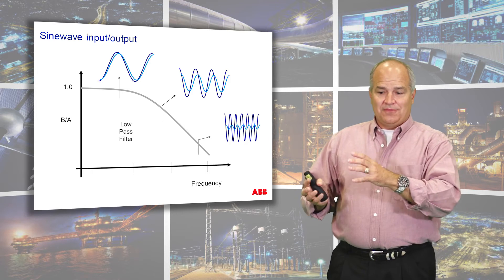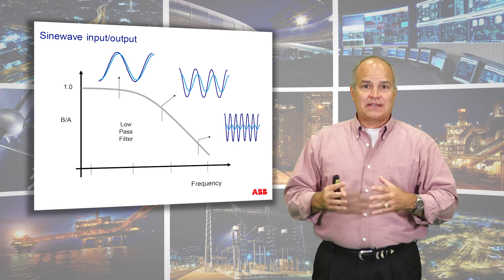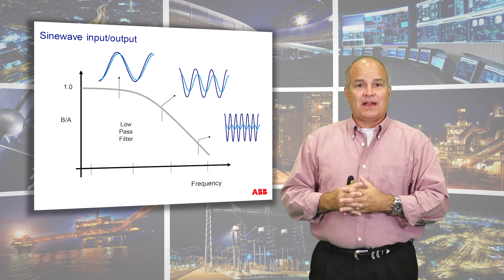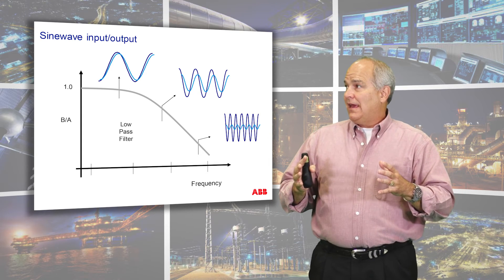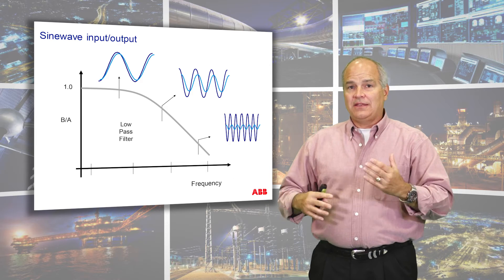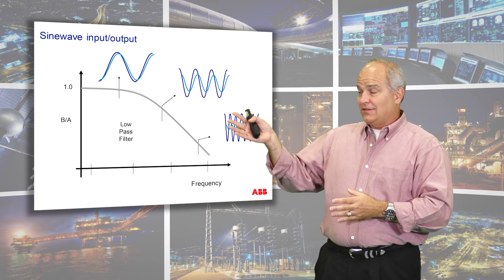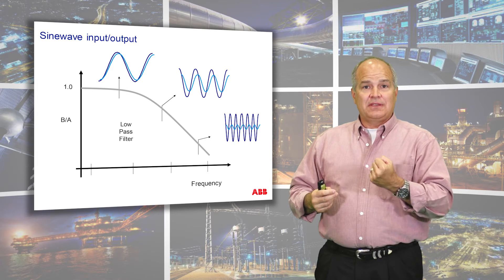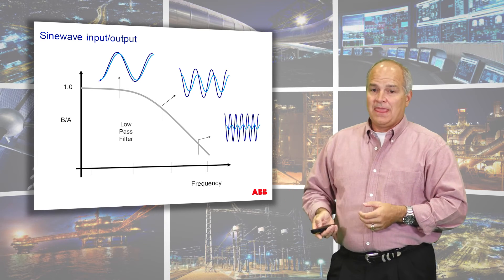I had an example where they were doing a three-level cascade loop and they hadn't separated the loops by enough time. The outer loop would oscillate, then the inner loop, and they just couldn't fix it. It had to do with this: we were driving the inner loops faster than they could physically keep up.